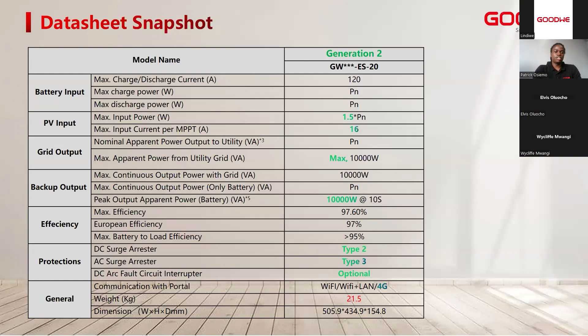In terms of scalability, the ESG2 allows expansion of the installed system in a master-slave topology. In this sense, you can parallel 3 pieces of the ESG2 to make, on the higher side, 18 kilowatts, and you'll be utilizing the EasyLink communication module when paralleling the system. When you use 3 pieces of the ESG2, you'll utilize the UPS switching level time. And mind you, that's not the end of it. You can still parallel up to 16 pieces of the ESG2, but then the operation mode of this inverter will be reduced to EPS switching level. All of these work in master-slave mode with the master inverter being connected to the smart meter to ensure the zero export limitation and load monitoring at the grid incomer.